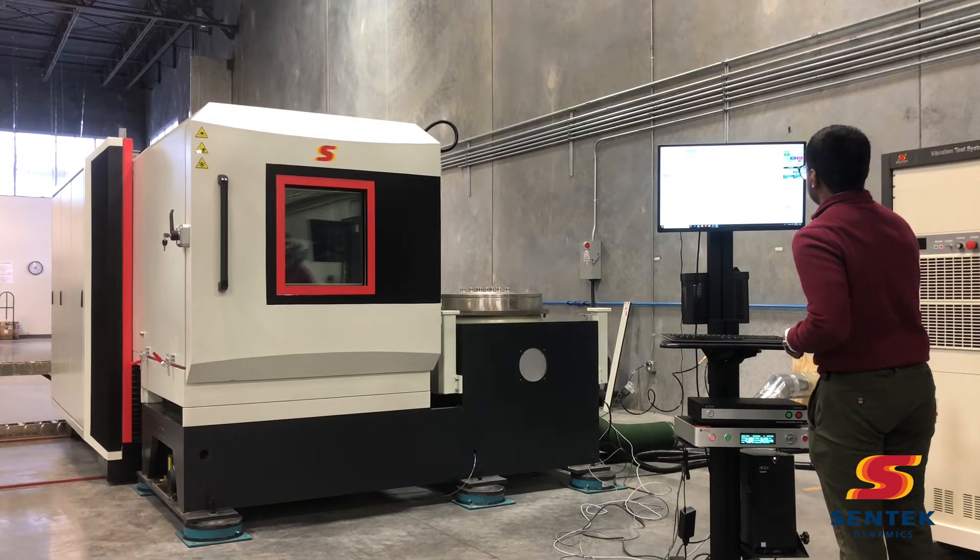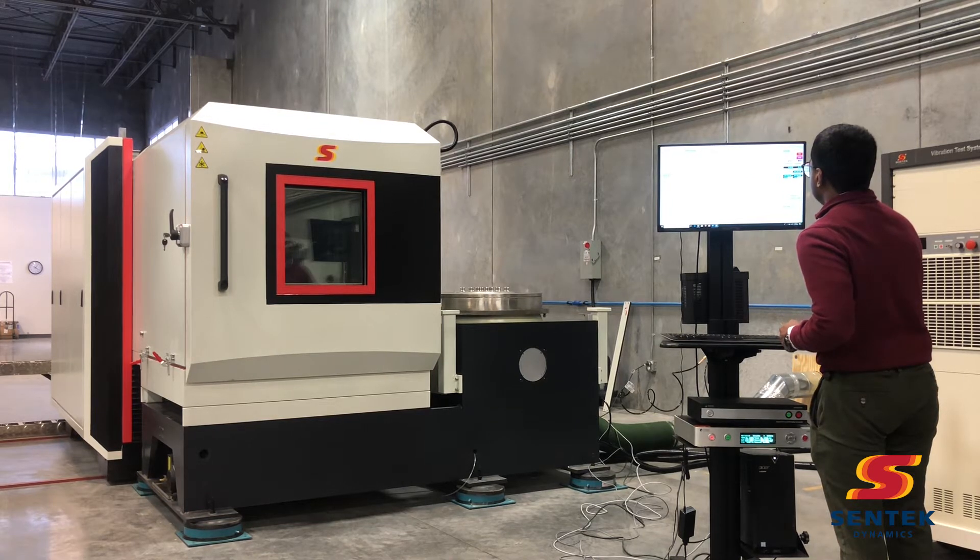This particular system is configured with a Sentek Dynamics M3240A electrodynamic shaker that is rated at 7,050 pound-force sine and random, and over 14,000 pound-force for shock testing.